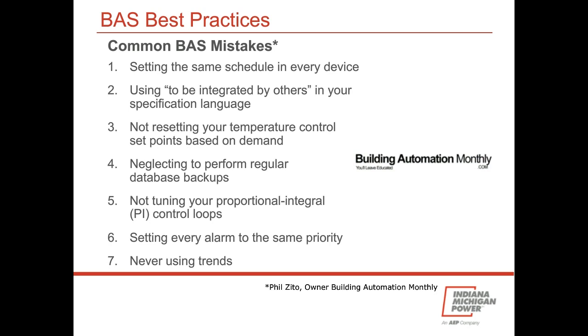So don't set the same schedule in every device. About 70% of buildings have just 1 to 3 schedules set for the entire building. But a building has a lot of different spaces - hallways, maybe a library, a gymnasium or workout facility, classrooms, office space, lobbies. So a big mistake is not tapping into the ability to customize the system - HVAC, lighting, whatever - for the different space types.